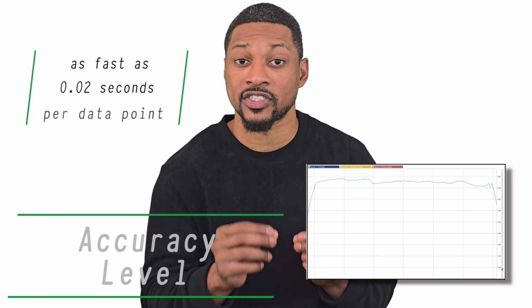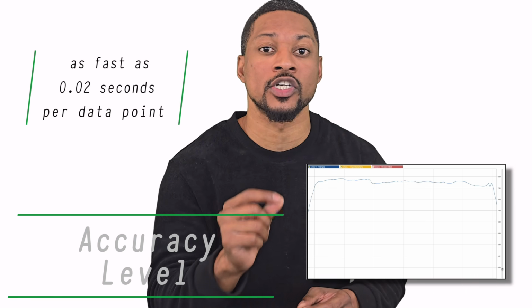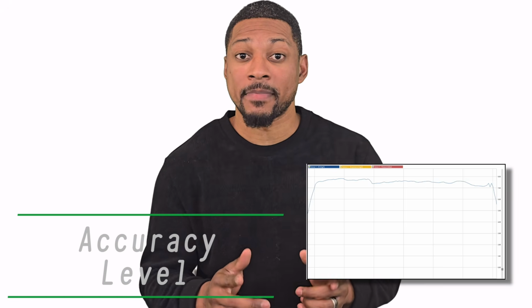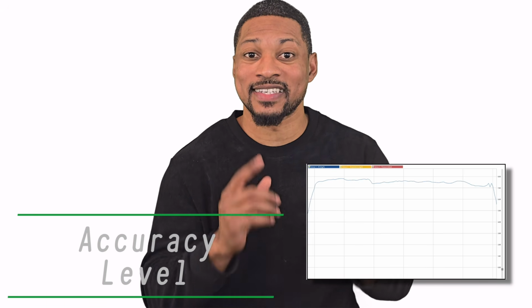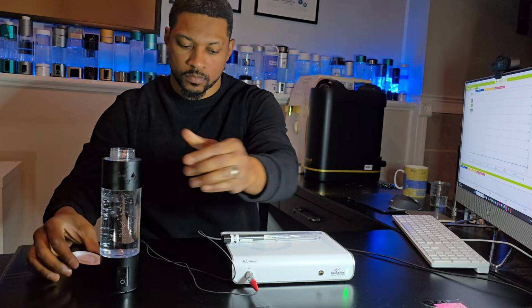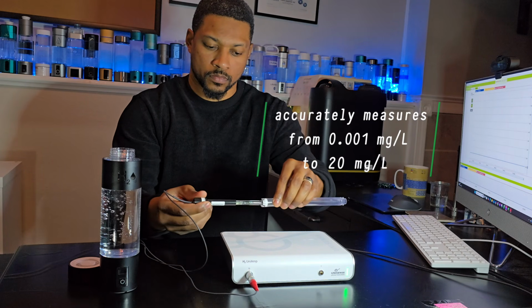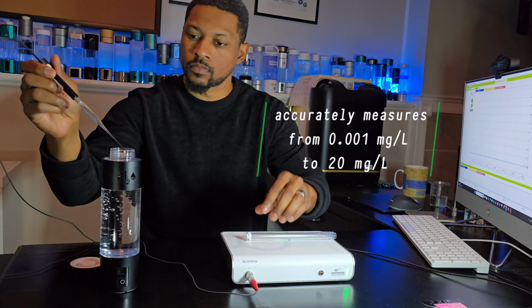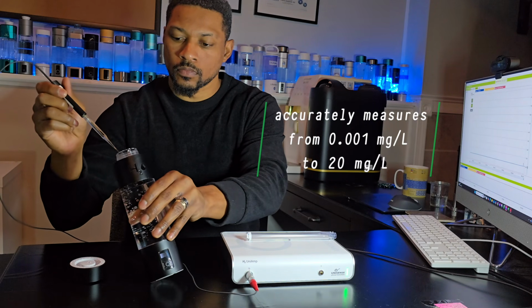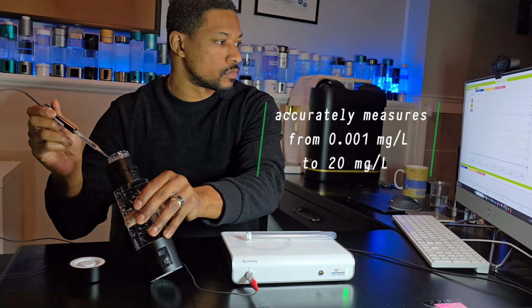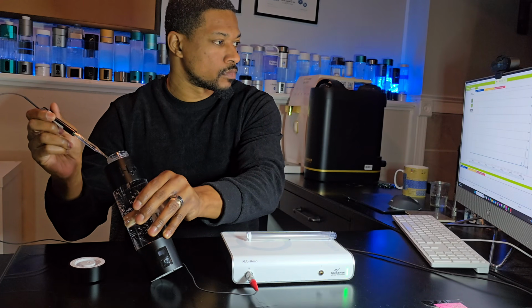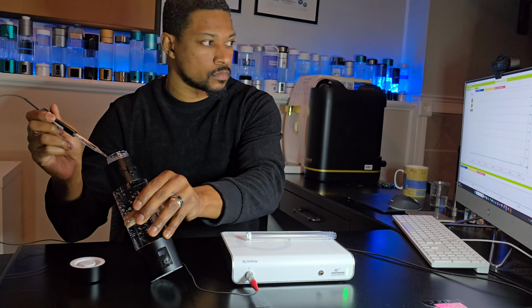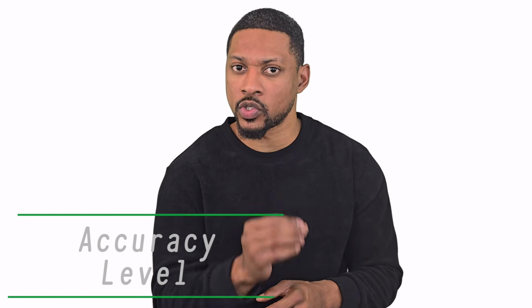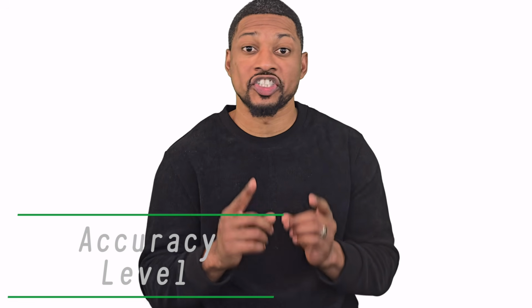It can capture changes in hydrogen gas concentration as fast as 0.02 seconds per data point. That means we can watch hydrogen gas concentrations rise, stabilize, and decay in real time. Our custom designed Unisense H2 microsensor can accurately measure dissolved hydrogen concentrations ranging from 0.001 milligrams per liter up to 20 milligrams per liter of dissolved molecular hydrogen. When calibrated against certified gas standards, its accuracy is comparable to GC. A key distinction between the Unisense and the GC is that the Unisense measures only dissolved molecular hydrogen, where GC measures both dissolved and quasi-dissolved molecular hydrogen.